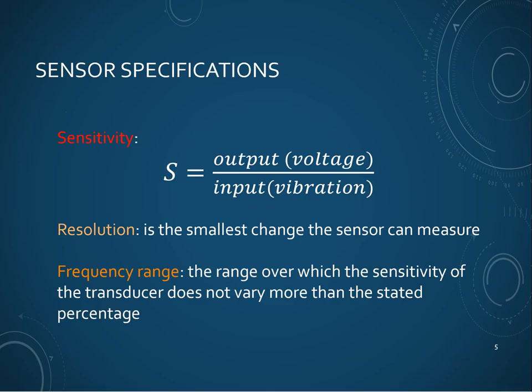In the sensor and data acquisition world, whenever you acquire a new sensor device, these devices come with data sheets that have many specifications. Common specifications include sensitivity, resolution, and operational frequency range. Sensitivity is a calibration factor between the measured output voltage and the input vibration — which could be accelerations, velocities, or displacements. Resolution is the smallest change that a sensor can measure. Frequency range is the range over which the sensitivity of the transducer does not vary more than a stated percentage; outside that range, environmental factors such as temperature can change the sensitivity significantly.